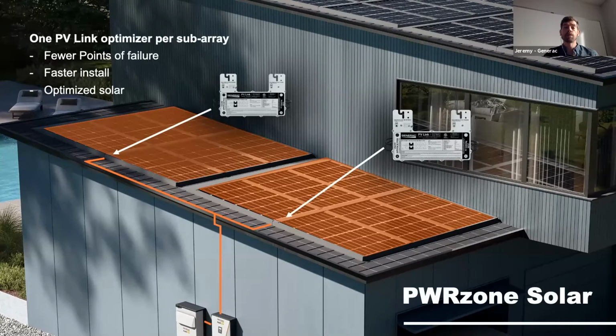And despite having fewer electronics on the roof, one thing people are frequently afraid they'll miss out on is shade performance, right? PWRzone still yields excellent shade performance because we work with the solar modules and their bypass diode capabilities, and in full sun, even better performance than per-module power electronics. A single string can carry up to 7.5 kilowatts, so you're going to do a lot fewer wire runs back to the inverter as well with this system.